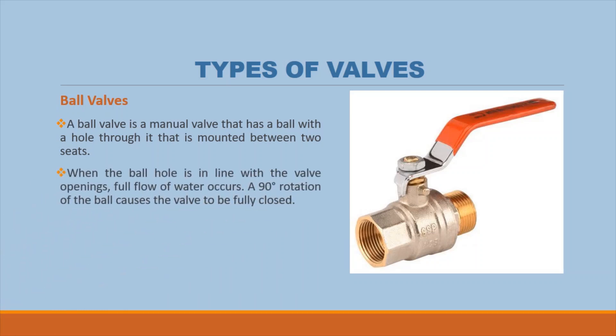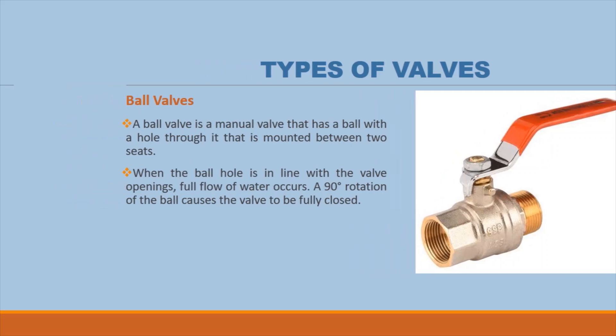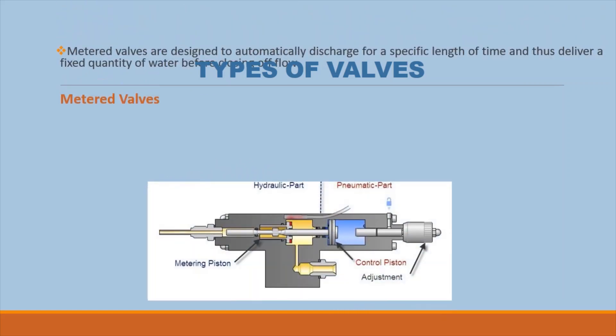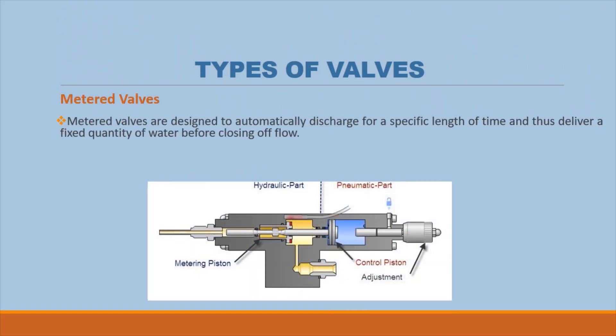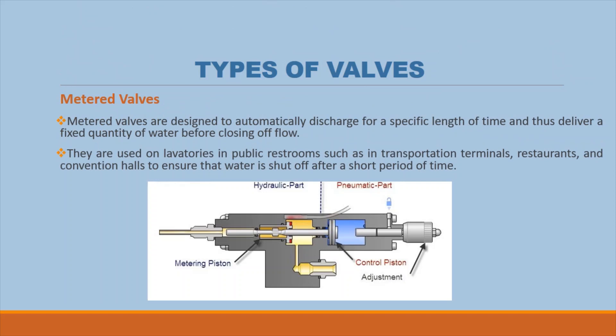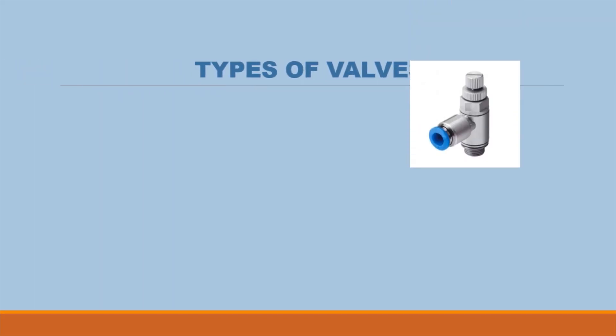Ball valves: a ball valve is a manual valve that has a ball with a hole through it, mounted between two seats. When the ball hole is in line with the valve openings, full flow of water occurs. A 90-degree rotation of the ball causes the valve to be fully closed. Metered valves are designed to automatically discharge for a specific length of time, delivering a fixed quantity of water before closing. They are used on lavatories in public restrooms such as transportation terminals, restaurants, and convention halls to ensure water is shut off after a short period.